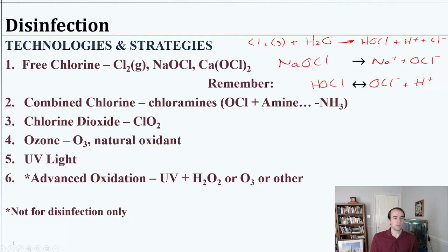And this is actually what we use intentionally for our residual chlorine dosing. So we want a chlorine residual in our pipes to keep the pipes clean, or at least prevent bacteria from repairing themselves after the disinfection. We want some sort of residual effect there. And so chloramines are what we add, and the way we get them is by reacting this free chlorine with some sort of ammonia. It could be NH3 directly. These could react with organic matter groups that have an amine group, and then you get some sort of chloramine with other stuff attached.